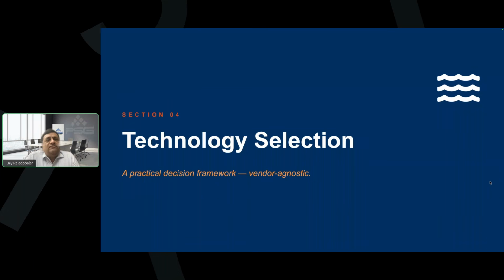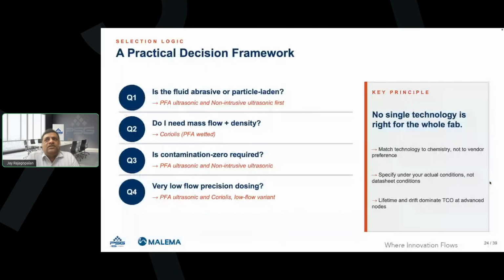So in the technology selection framework, after discussing that, I tried to keep the products as vendor agnostic as possible. You can ask questions later if there is anything specific to a particular product or technology. A decision framework would be like, is the fluid abrasive or particle laden? In such cases, PFA ultrasonic, or non-intrusive clamp-on ultrasonic, could be a first choice. Do you need a mass flow for more accurate blending? Is concentration or density measurement critical? If that is important, obviously a PFA Coriolis mass flow meter or flow controller could be a choice.